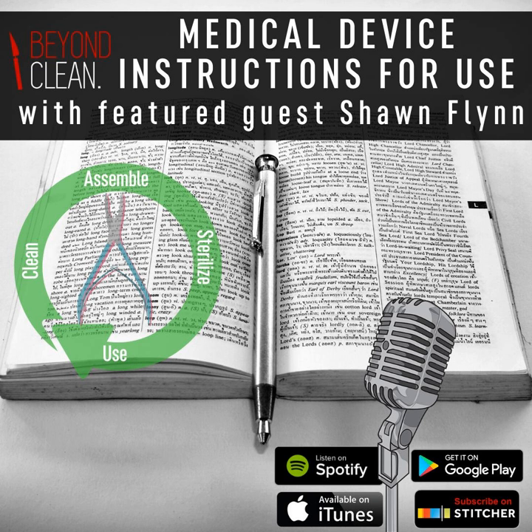It definitely does, because one of the major challenges with having all these different cycles is, what's the rule around running these devices through the sterilizer? It's not like a min and a max, it's tested at an exact cycle time. So how do people handle that with all these varied cycle times across different devices? They kind of make it fit what they're trying to achieve.